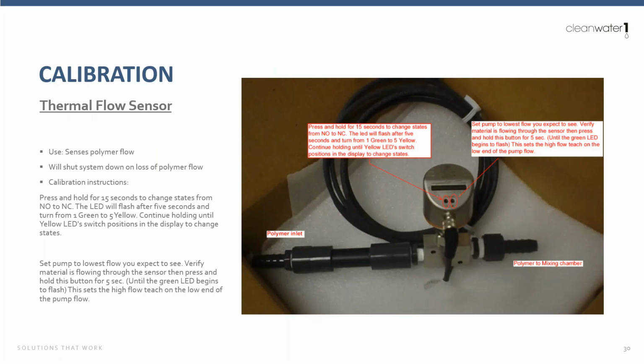These do need to be calibrated. They're calibrated out of the factory. However, every now and then they need to be calibrated in the field. Basically, what we're doing is we're setting these teach points, the low and high teach, based off of the pump rate. And so the specific pump rate is going to dictate what settings this thermal flow sensor is at. Every now and then these do need to be calibrated.